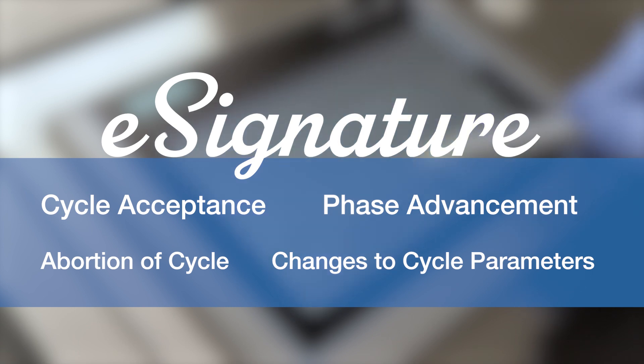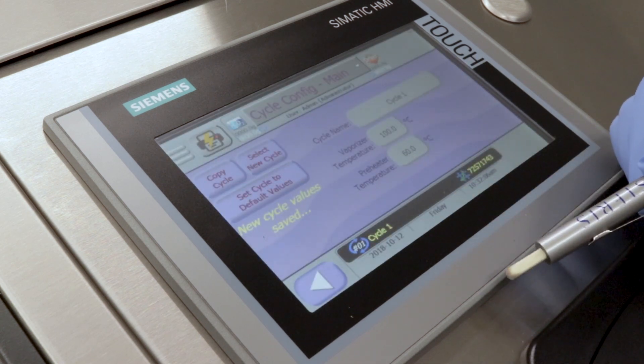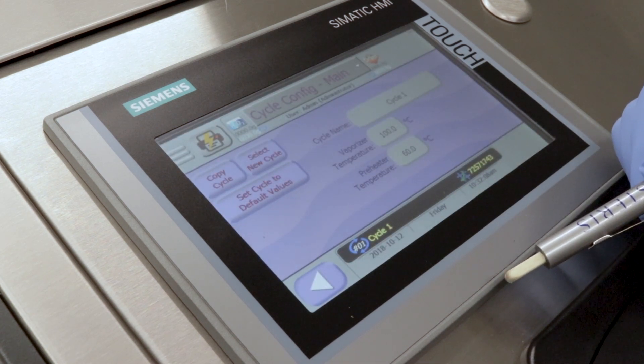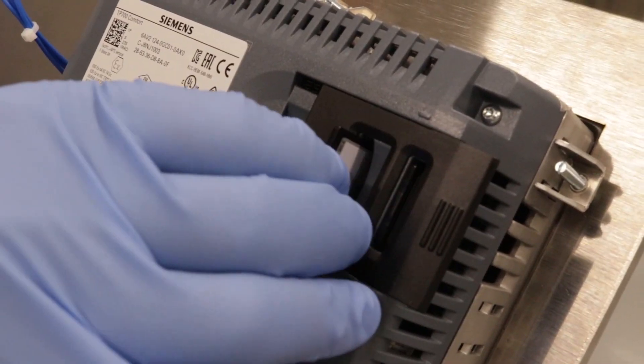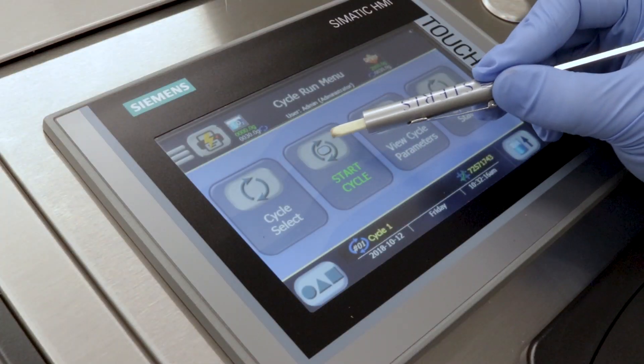Another important feature for 21 CFR Part 11 compliance is audit trail. The Steris audit trail feature tracks users' actions through all critical functions as appropriate for the equipment type. All information captured in the audit trail is archived onto a memory card in the HMI in CSV file format. Actions such as cycle initiation, a change in the cycle parameters, login attempts, and alarm acknowledgments will be captured.